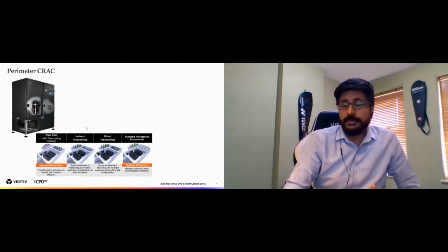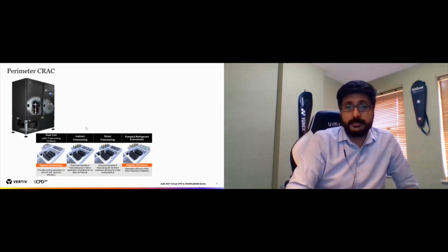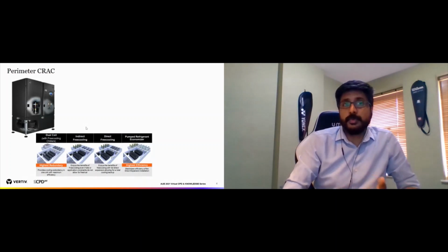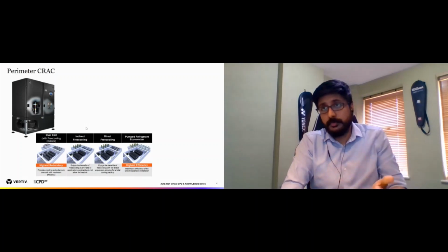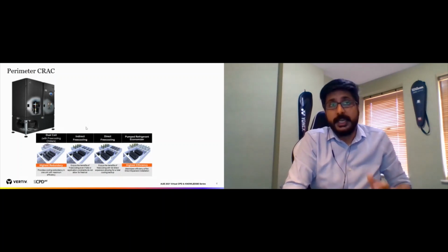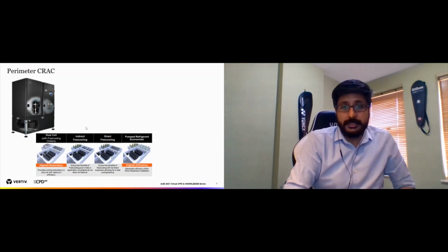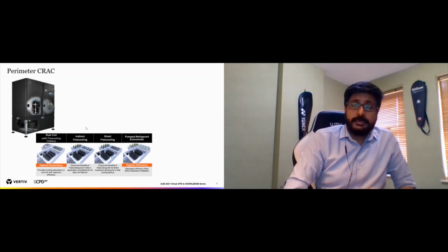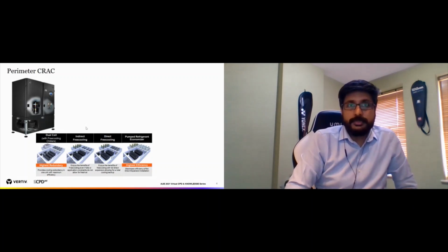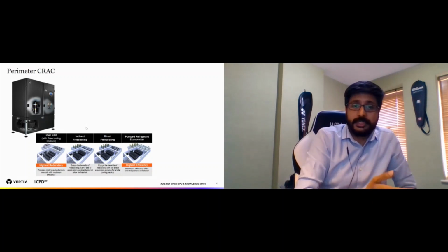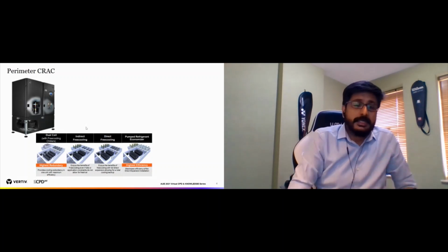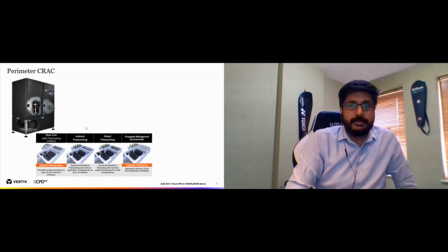So then the option was to bring in free cooling, and that's where the indirect free cooling option comes in. Again there are two cooling coils inside the unit, and there are water cooled condensers. When the ambient becomes favorable, the dry coolers used with these water cooled condensers can act as a chilled water cooling unit, and the cold water goes into the cooling coils in the rooms. So that's where indirect free cooling comes in. To take one step further, where the ambient becomes favorable again, we have the option of direct free cooling. In the north of UK, for example, we have ambient less than 20 degrees throughout the year, or even close to 5 to 10 degrees. We can have direct fresh air coming into the rooms, where you don't have to run the DX compressors at all.